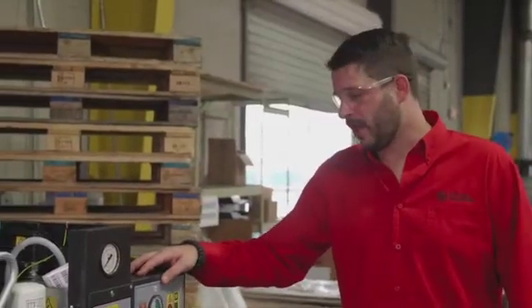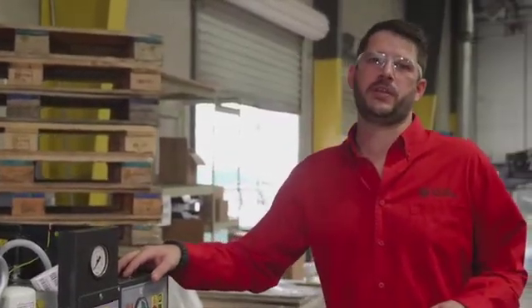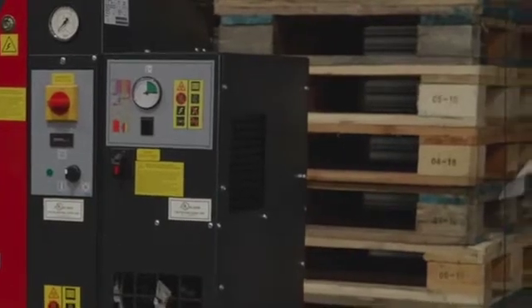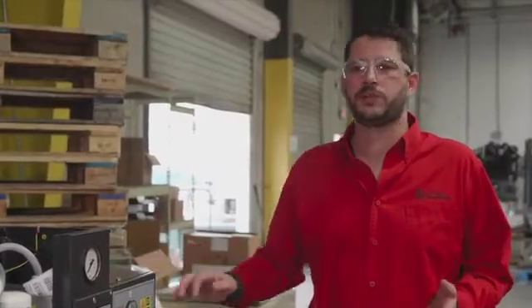On models with an integrated dryer there are two main maintenance items to look at. One is going to be your condenser. Depending on how dirty your shop is you may need to clean your condenser a little more frequently, but typically about once a month you'll just need to take a little compressed air and blow out your condenser.